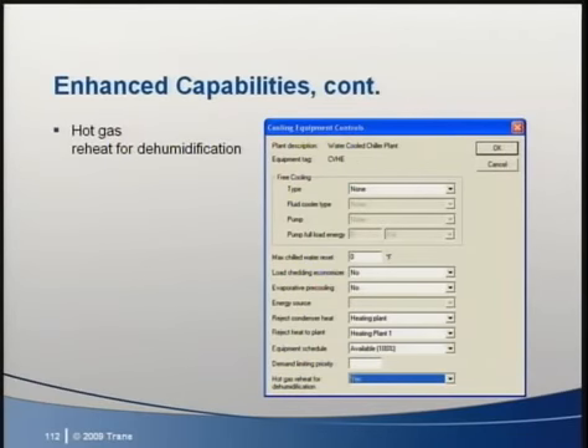During the hot gas reheat cycle, there is ambient relief due to the fact that the refrigerant is being cooled much lower than ambient conditions, and therefore the equipment should run more efficiently. The maximum amount of hot gas reheat available is equal to the heat transferred from the air to the evaporator load plus the actual compressor heat of compression.